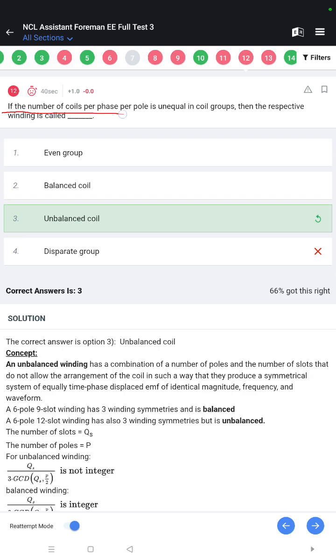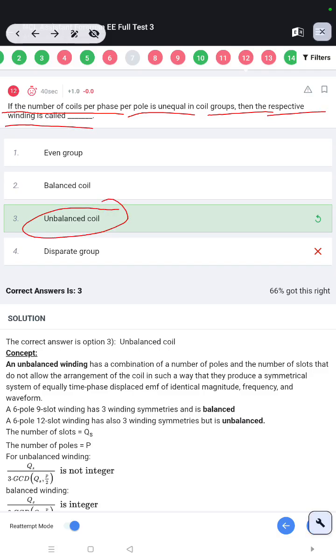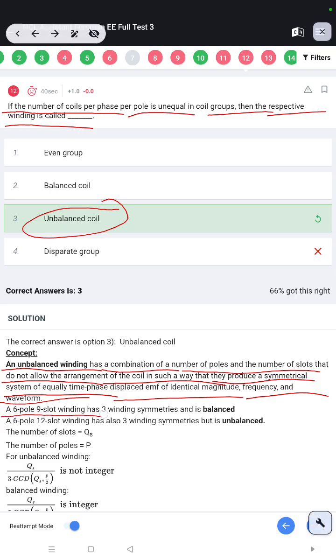If the number of coils per phase per pole is unequal in the coil groups, then the respective winding is called an unbalanced winding. An unbalanced winding has a combination of number of poles and number of slots that does not allow the arrangement of the coils in such a way that they produce a symmetrical system of equally time-phase displaced EMFs of identical magnitude, frequency, and waveform. A 6-pole 9-slot winding has 3 winding symmetries and is balanced. A 6-pole 12-slot winding also has 3 winding symmetries but is unbalanced.